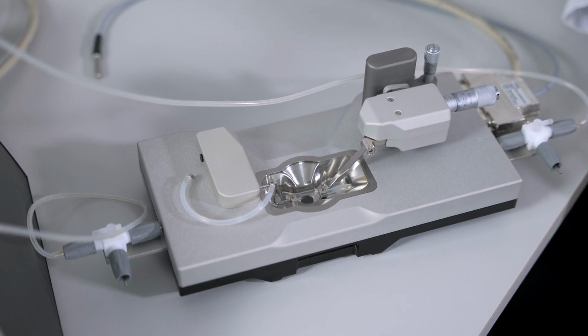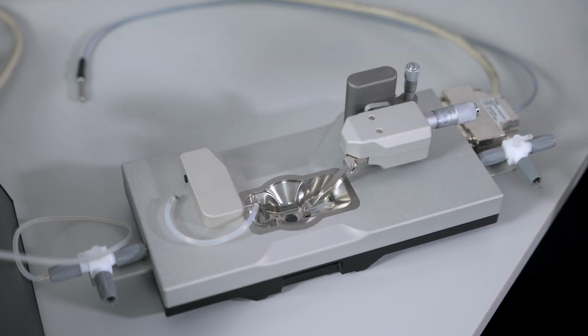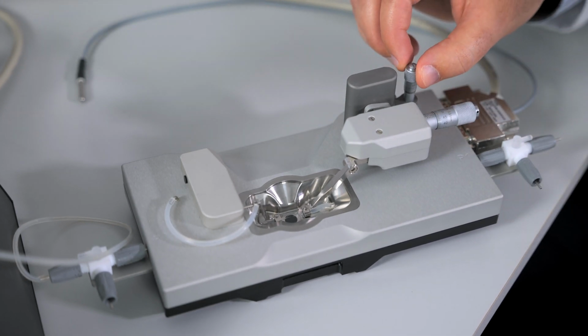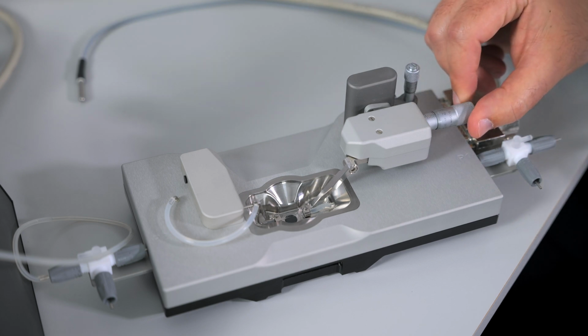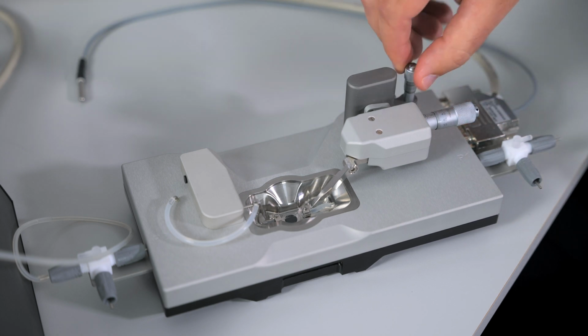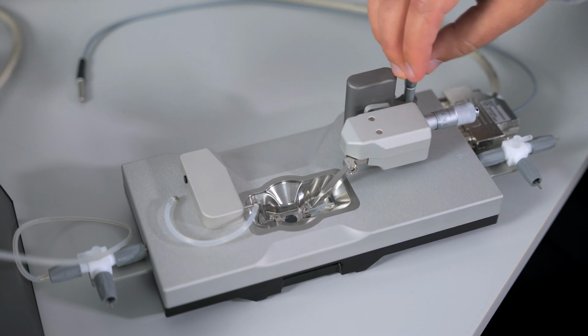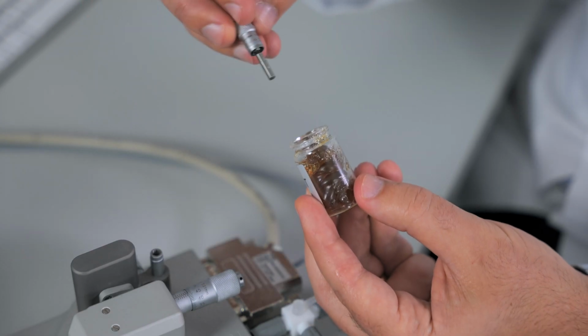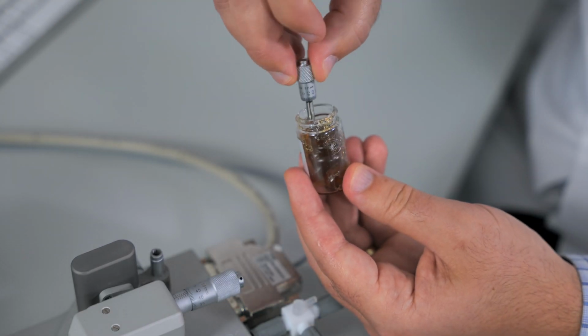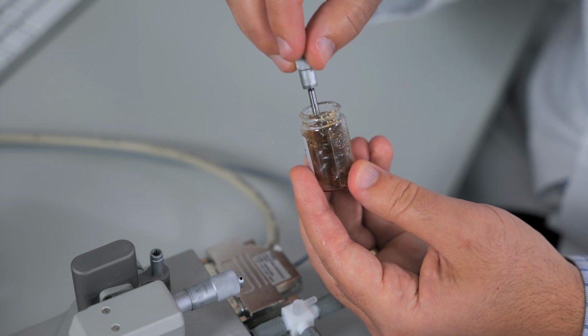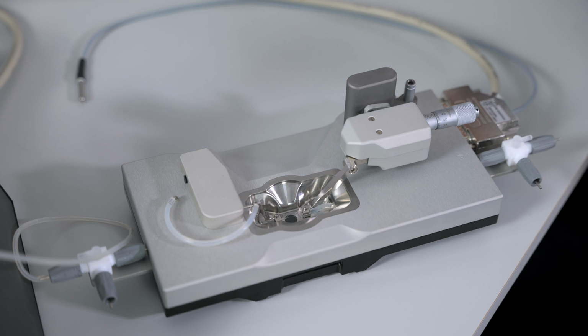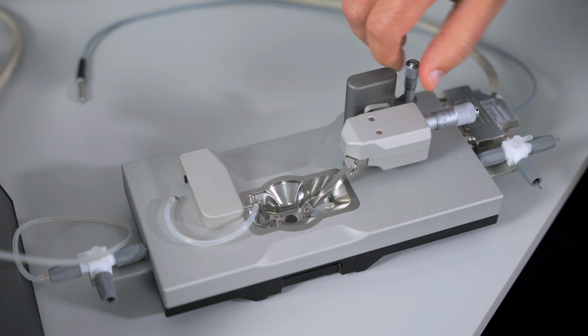Flush each side while keeping an eye on the pressure, and then make sure to push air through again at the end. If you notice that any of the 3 micrometers start to be a little more firm and not fluid when you are adjusting them, you can back them out all the way until they come loose. And you can actually stick these into the brown grease that came with your system as well. All you need to do is stick it in there, get some brown grease on there, and then screw the micrometer back in place.